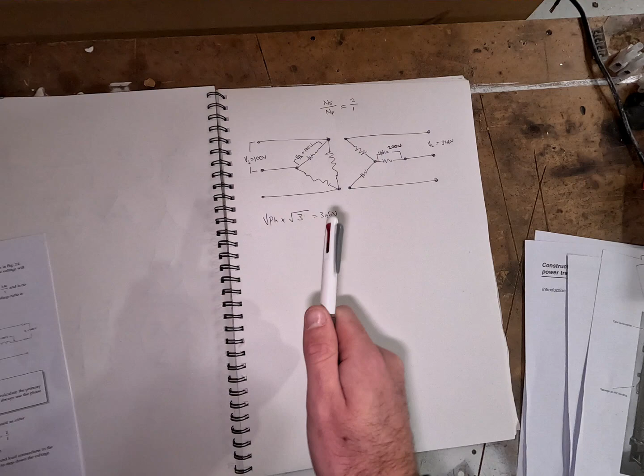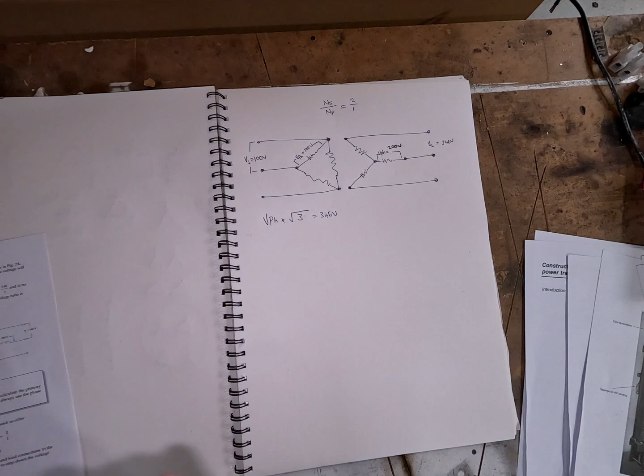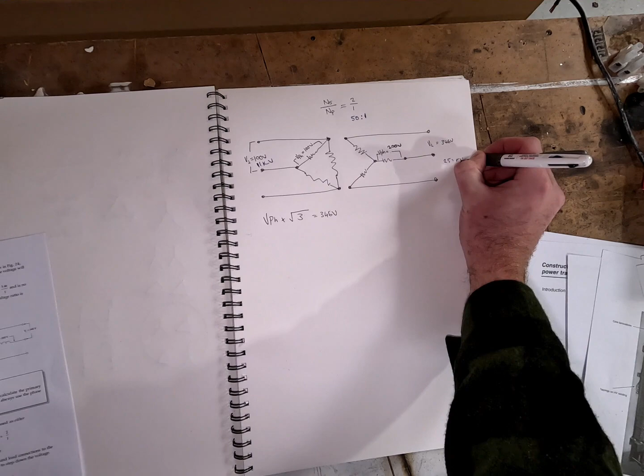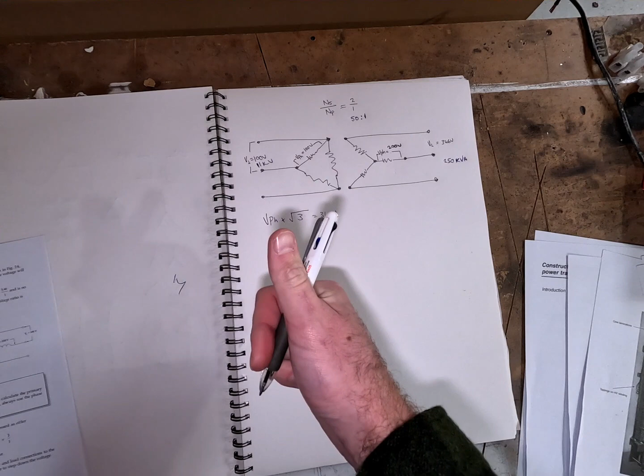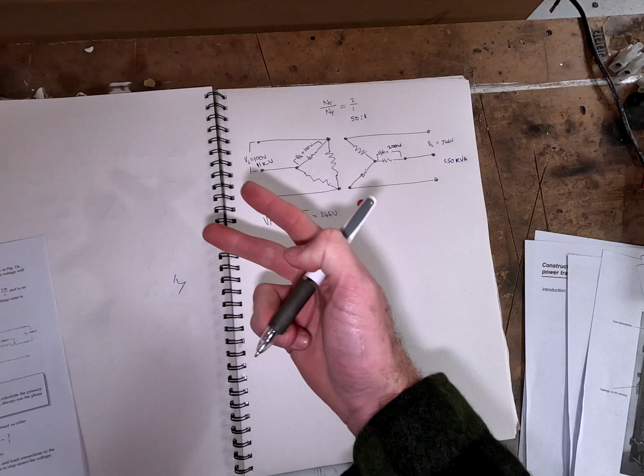Now I'm going to use a slightly different scenario because I've got one here that I can work out of my apprentice workbooks. Let's say that this here is, I will do this in blue, 11 kV between here on the line voltage. It's a 50-to-1 ratio. The output is 250 kVA. Okay, so that's all the information we know, and I'm going to work you through getting the primary line current, the secondary line voltage, the secondary phase voltage, and the secondary line current.